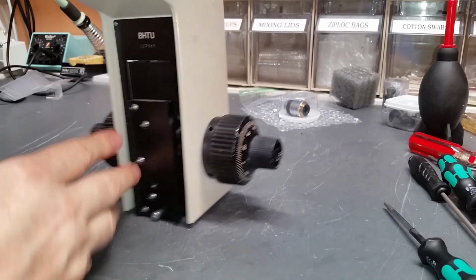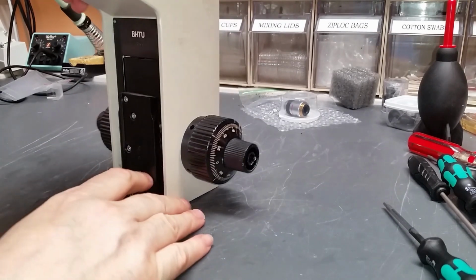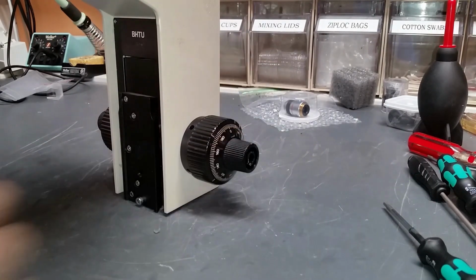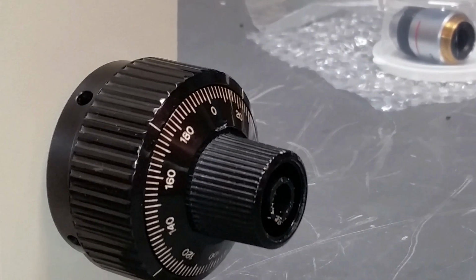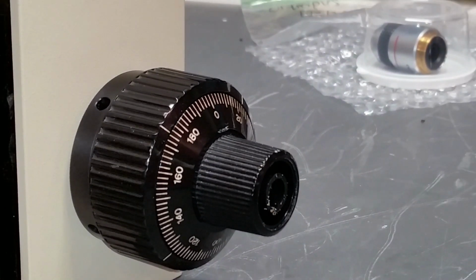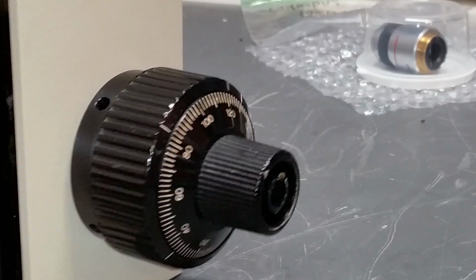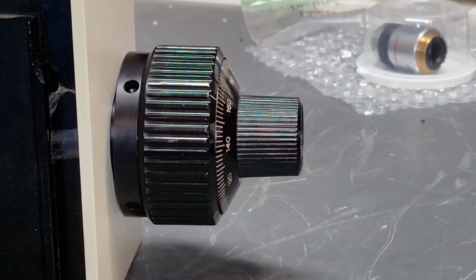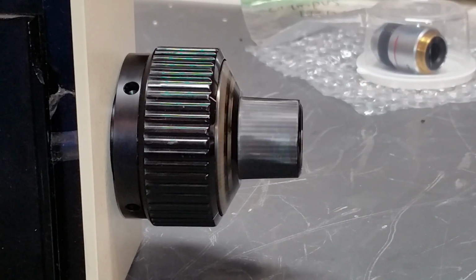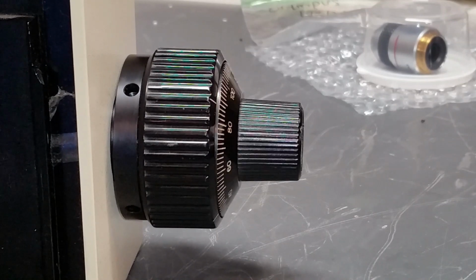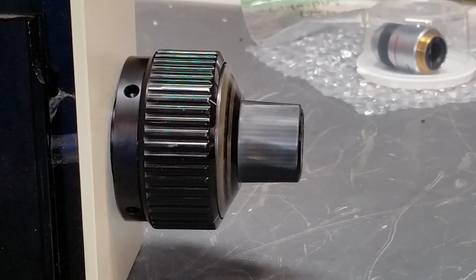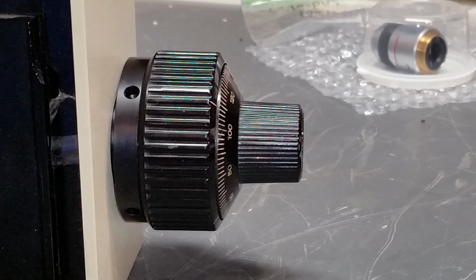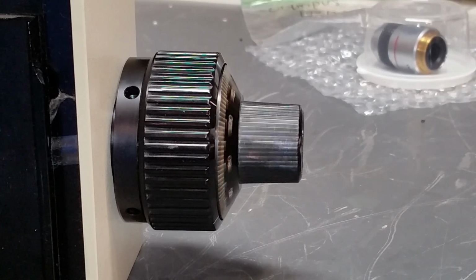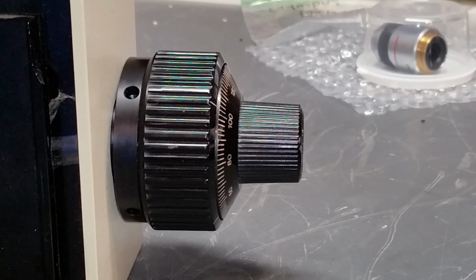The reason I'm shooting this video is to show you, if you look at this fine focus knob here, if I zoom in just a little bit for you, so I rotate that on the other side. You can see it's got a little bit of a wobble to it, and the reason for that is because the fine focus shaft has been bent at some point during the life of this thing. It's taken an impact, perhaps during shipment, or who knows, but for whatever reason, that is bent.